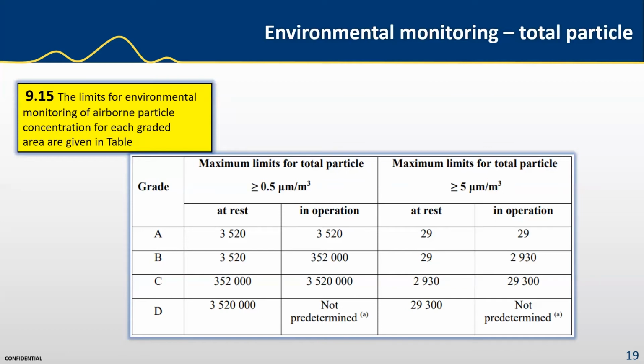Note 2, which isn't shown, but I'm going to talk about it: the occasional indication of macro particle counts, especially greater than or equal to 5 microns within grade A, may be considered to be false counts due to electronic noise, stray light, coincidence loss, etc. However, consecutive or regular counting of low levels may be indicative of a possible contamination event and should be investigated. Such events may indicate early failure of the room air supply filtration system, equipment failure, or may also be diagnostic of poor practices during machine setup and routine operation.